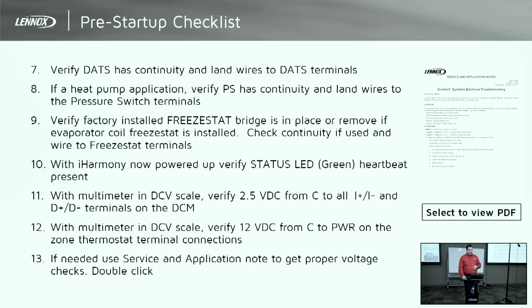Another thing that you'll look at here for communication is this 2.5 volts DC. We're checking for proper communication between all your communicating components. You're checking common to I+, common to I-. On your zone sensors, all your communicating equipment, that's going to be your money in the bank as far as your comm signal. If that's 2.2 or 2.3, or if it's 2.7 or 2.8, that can be an indication of a problem. And it talks about this service note here.